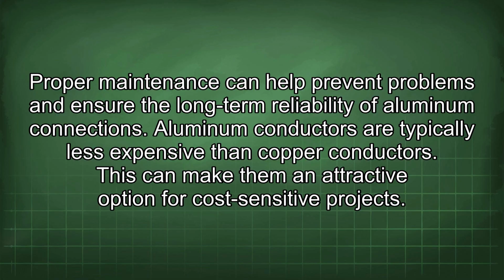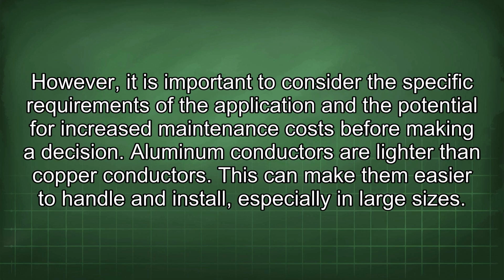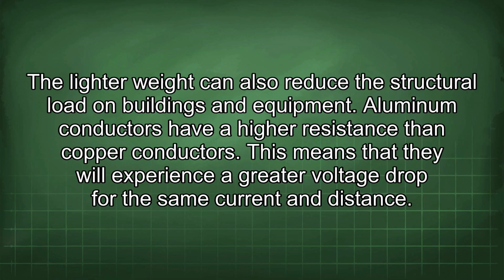Aluminum conductors are typically less expensive than copper conductors. This can make them an attractive option for cost-sensitive projects. However, it is important to consider the specific requirements of the application and the potential for increased maintenance costs before making a decision. Aluminum conductors are lighter than copper conductors. This can make them easier to handle and install, especially in large sizes. The lighter weight can also reduce the structural load on buildings and equipment.